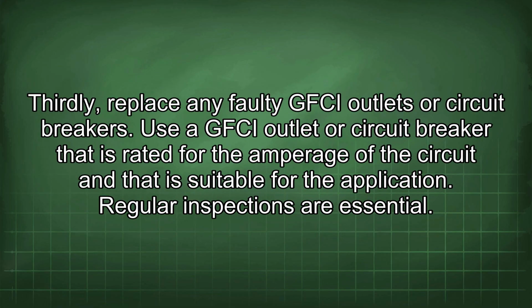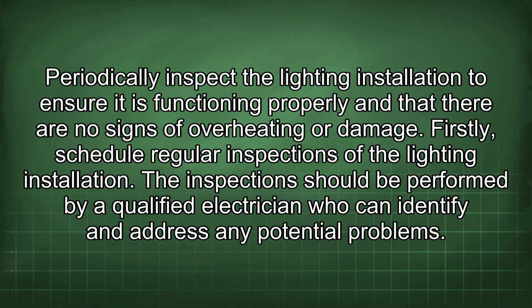Thirdly, replace any faulty GFCI outlets or circuit breakers. Use a GFCI outlet or circuit breaker that is rated for the amperage of the circuit and that is suitable for the application. Regular inspections are essential. Periodically inspect the lighting installation to ensure it is functioning properly and that there are no signs of overheating or damage. Firstly, schedule regular inspections of the lighting installation.